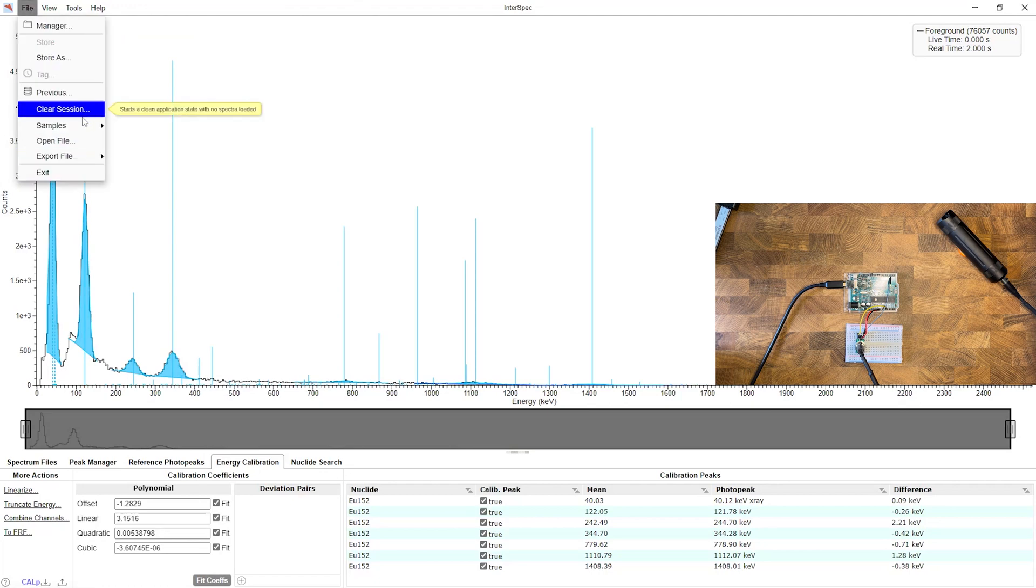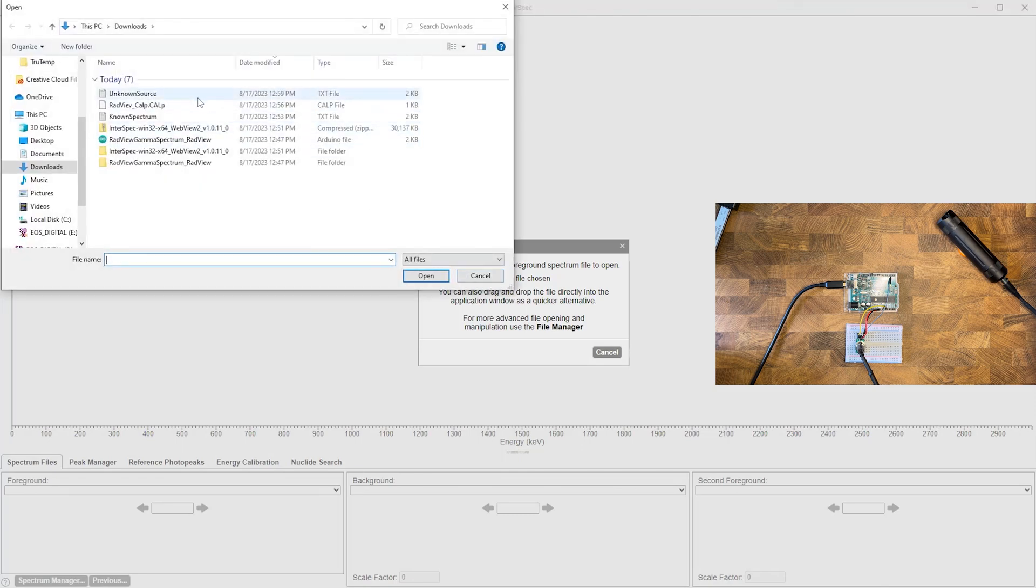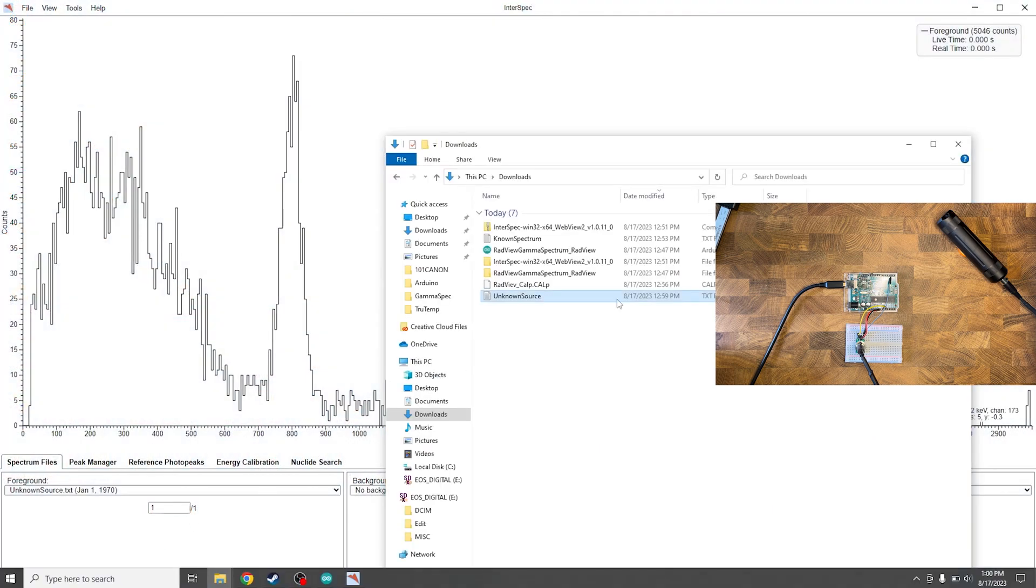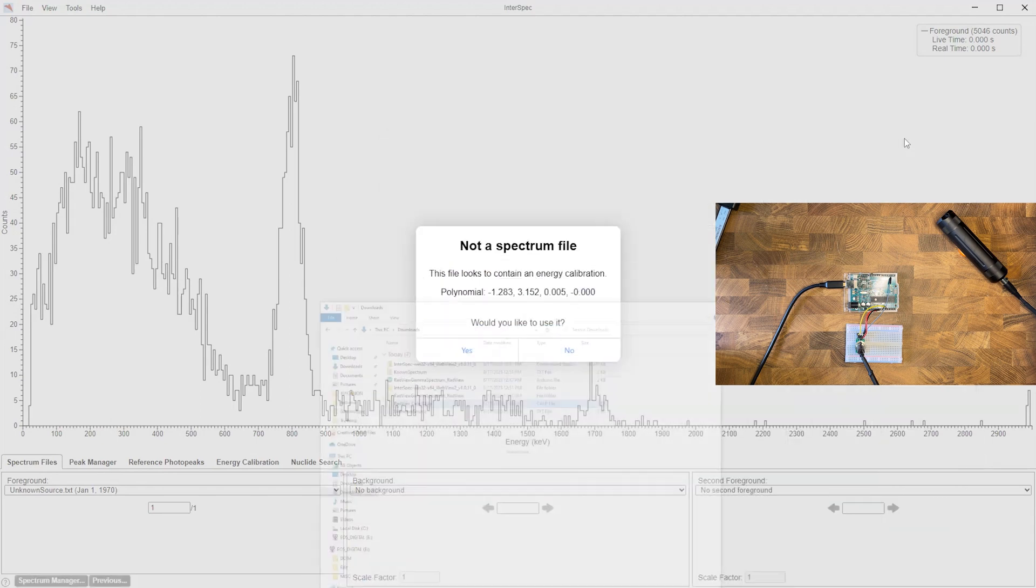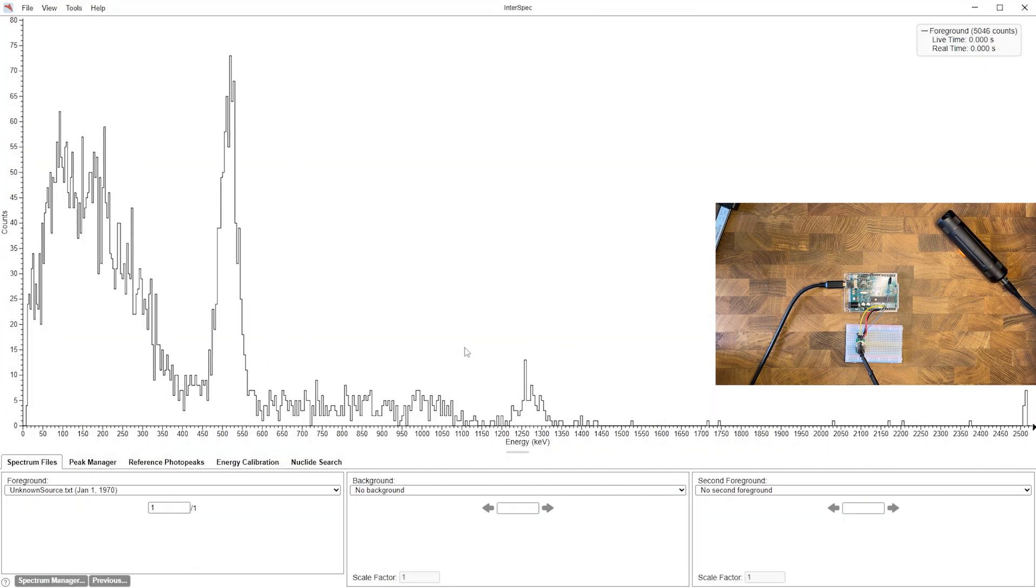So from there we can head back over to InterSpec and let's say we had a new session further down the line. So we're going to clear our session. So now we can go to file, open file, and then we can add our unknown source here. So here you can see a spectrum and it's uncalibrated currently because we started a new project. Luckily we have our calibration profile so if we head back over to our downloads we can see our RadView calibration profile. We can click and drag that onto our spectrum. When we do that it'll say it looks like that file has a calibration and we're going to hit yes we want to use it.